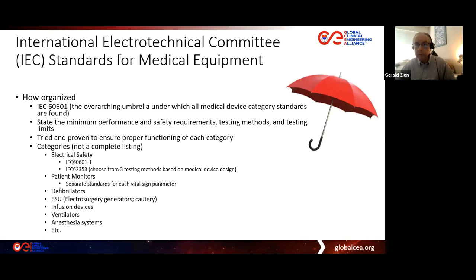All right, so 60601 is the umbrella. These state the minimum performance and safety requirements, testing methods, and testing limits that have been determined by the committees that sit on the IEC subcommittees. These are tried and true. They're proven. They've been used internationally for many, many years. But their categories cover almost every medical device that I have found when I look into them.